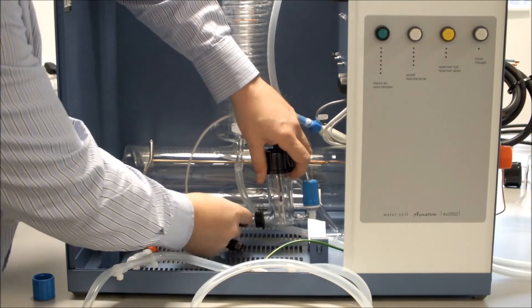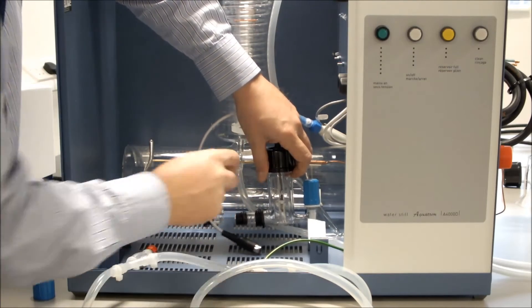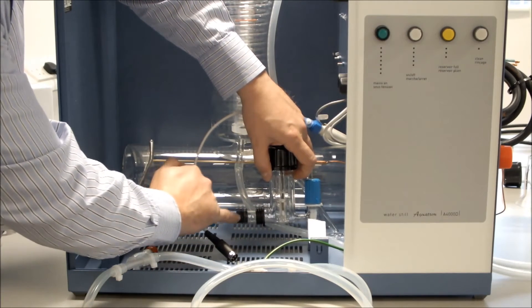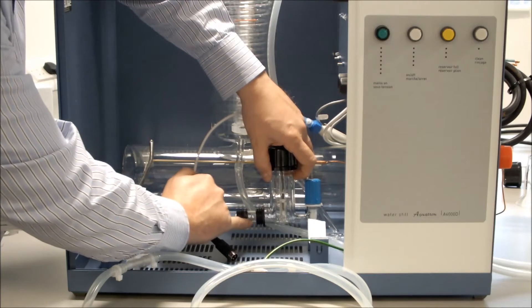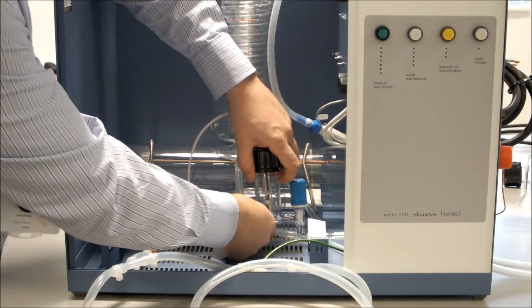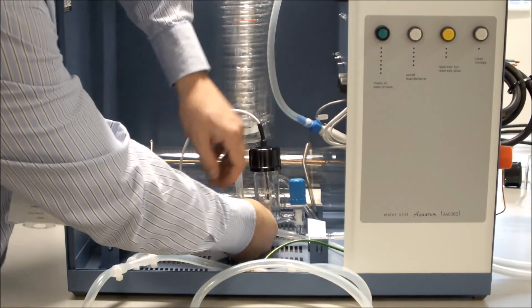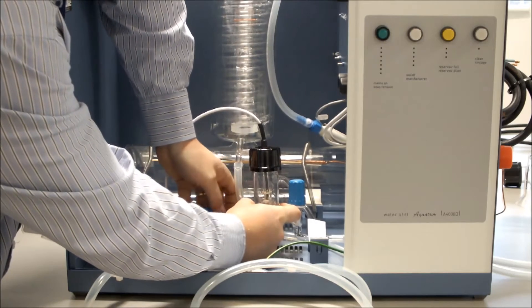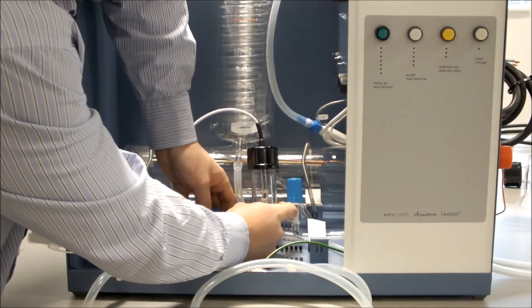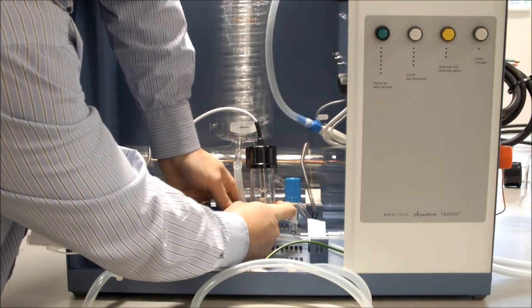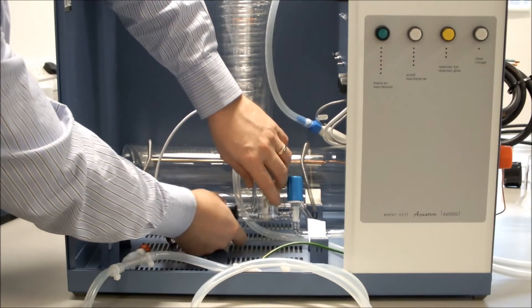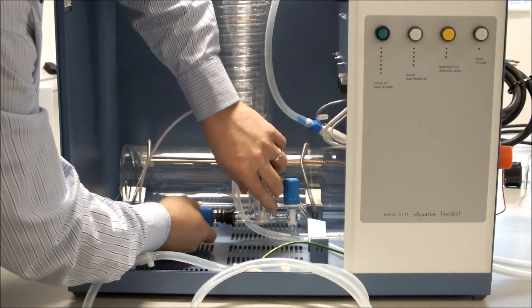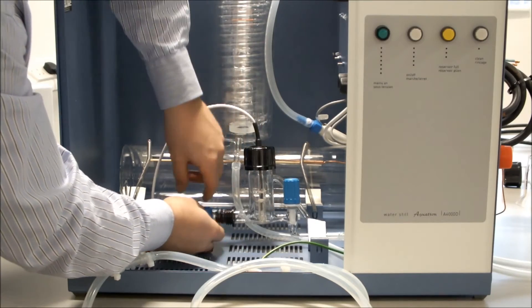First of all we put our split nut onto the boiler and also the center portion of our coupling. We then must make sure that the rubber sleeve is fitted inside the boiler level control and the boiler itself.